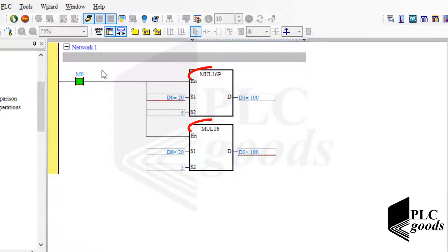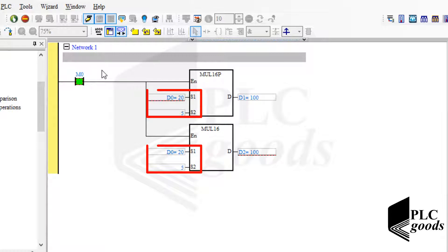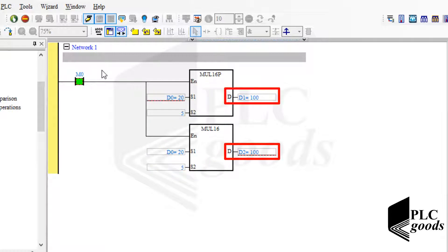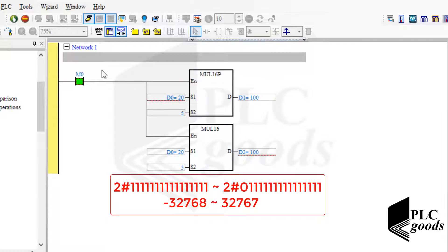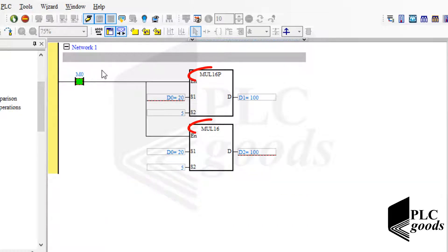Note that we can use these two instructions when the two inputs and also the result can be represented by 16 bits — from minus 32,768 to 32,767. Otherwise, these instructions may not calculate the correct answer.